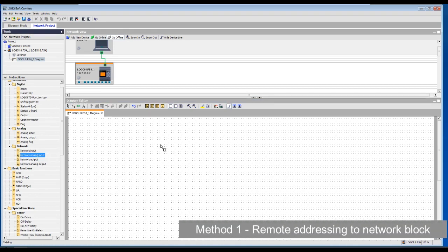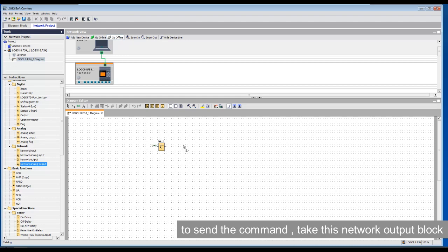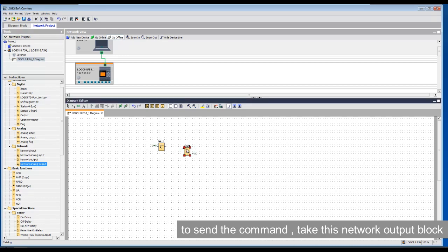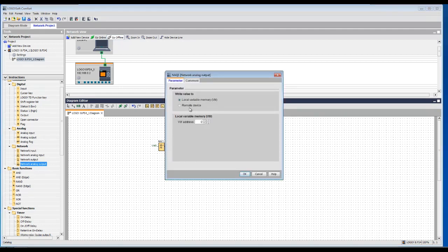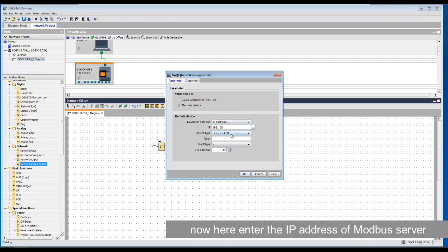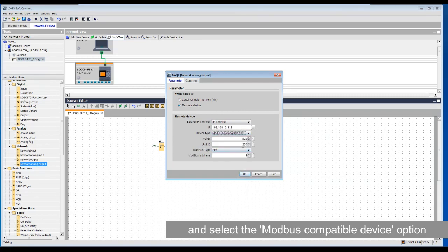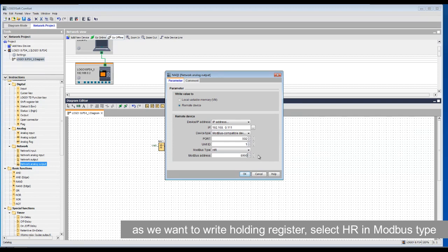In Method 1, I will directly define the remote address to the network block. Take this network output block, double-click on it, and select the remote device option. Now enter the IP address of the Modbus server and select the Modbus-compatible device in the device type. Also enter the port and Unit ID. Select HR for holding register and enter the address that we would like to write.